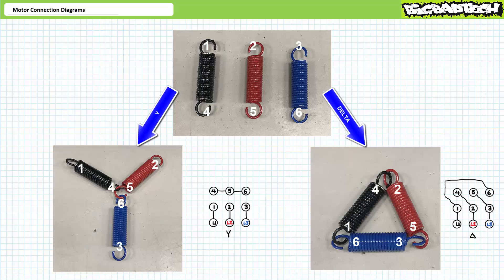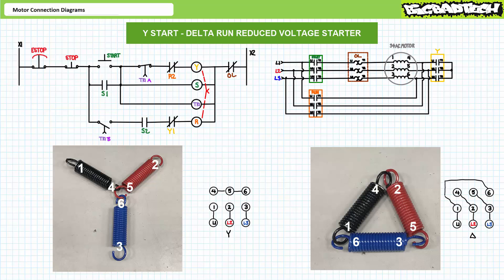A six-lead motor is slightly more flexible than a three-lead Y or three-lead delta because it can act as a Y or a delta depending upon the manner in which it is connected. An extremely popular reduced-voltage starting method known as a Y-start delta-run reduced-voltage starter takes advantage of this. As implied by the title, it starts the motor in a Y configuration so each winding experiences a smaller line-to-neutral voltage and draws smaller inrush current, then after a predetermined time the Y configuration is broken and reassembled as a delta so each winding experiences the larger line-to-line voltage. This two-stage start reduces inrush current and modifies the starting torque of the motor.